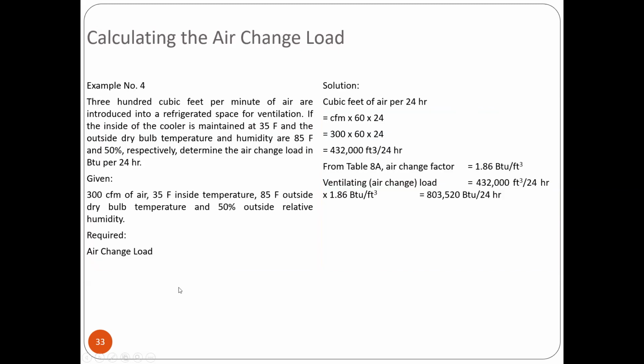So, example number 4. 300 cubic feet per minute of air are introduced into a refrigerating space for ventilation. If the inside of the cooler is maintained at 35 Fahrenheit and the outside dry bulb temperature and humidity are 85 and 50% respectively, determine the air change load in BTU per 24 hours. So given 300 CFM of air, 35 Fahrenheit inside temperature, 85 Fahrenheit outside dry bulb temperature, and 50% outside relative humidity. Required air change load.